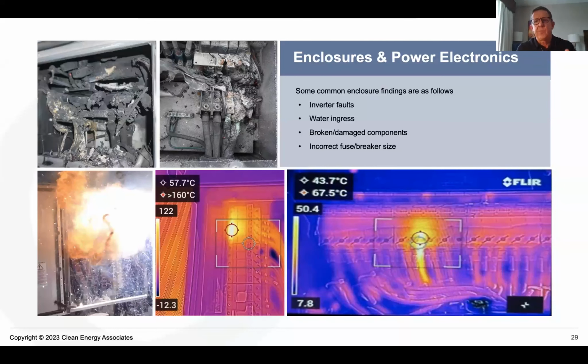Water ingress is very important, so close your enclosures properly. But power electronics, like rapid shutdown devices and inverters, we're doing a lot of thermal event investigation on them. That release of energy is on your roof, and we want to stay away from that. That's why if you gave me 3 hours to focus on what I would focus on first, it would be here, because there's more potential here.